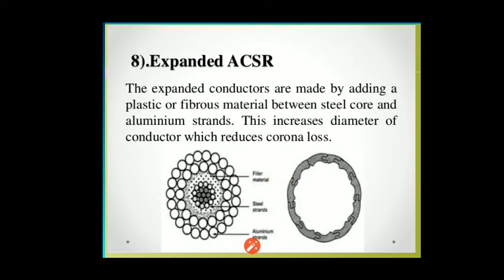Eighth, the expanded ACSR conductor. As shown in the diagram, expanded ACSR conductors are made by adding a plastic or fabric material between the steel core and the aluminium strands. This increases the diameter of the conductor, which reduces corona loss. It is one of the most effective designs used in ACSR conductors.